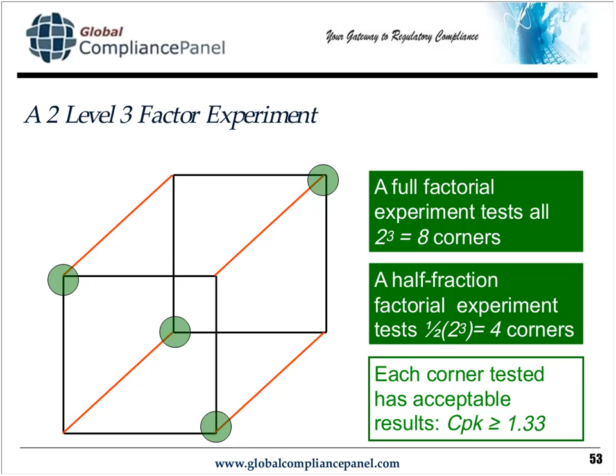The idea now is that every corner tested has acceptable results, CPK of 1.33. Those corners are going to be my challenge points. Those are going to be the worst case conditions. I'm going to find them through design of experiments. I'm going to test them as part of my OQ. And the claim then is that if I've got the worst case conditions, then anything inside this 3-dimensional box is going to be the worst case or better. And so things are going to operate satisfactorily anywhere inside the box as long as I can demonstrate they operate satisfactorily at the worst case corners.